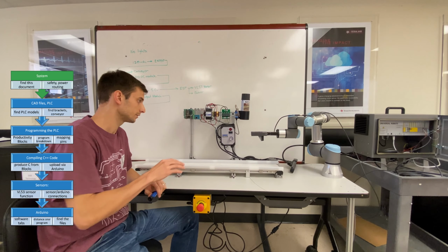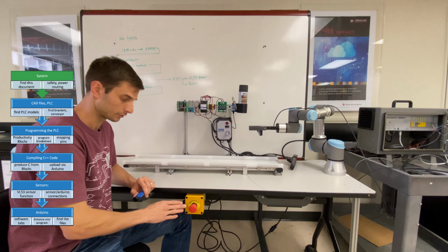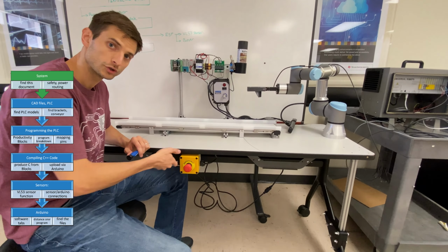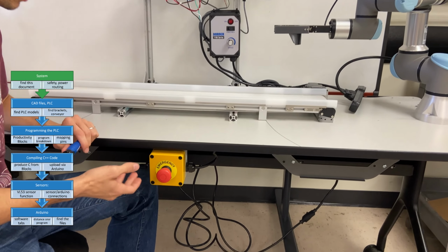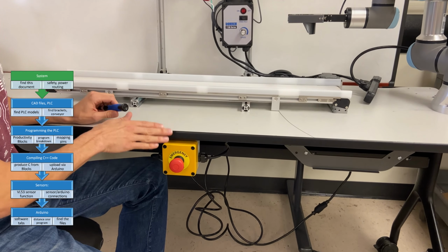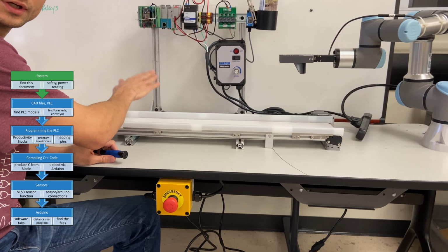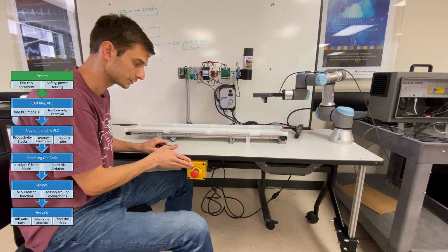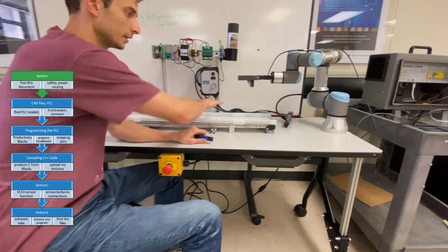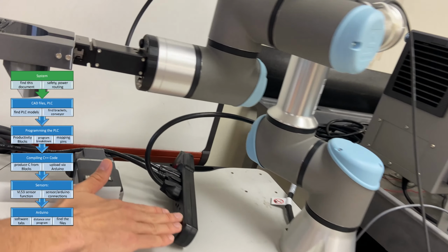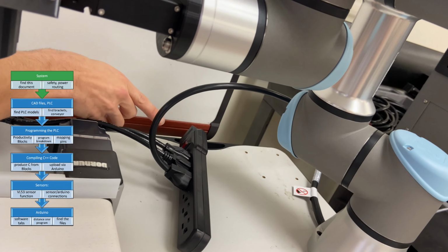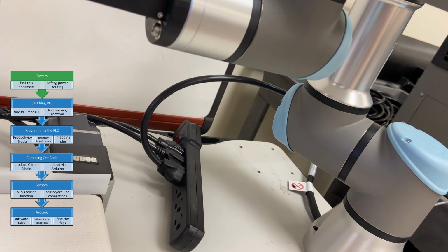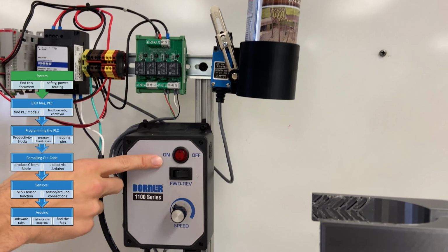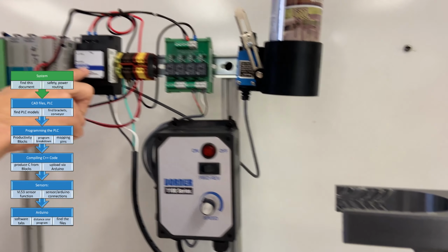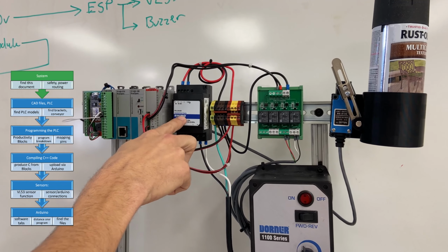The power comes into the system for this demo, all starting with this e-stop, which is a push-pull type. There's no switching, there's no rotating. The power is coming from the wall at 120 volts, and it passes through this e-stop first, and then it comes over to the power switch here. And you should see no LED there, and no LED on these other two modules, the conveyor module and the power supply for 24 volts.